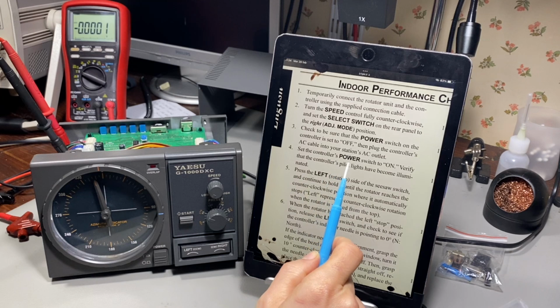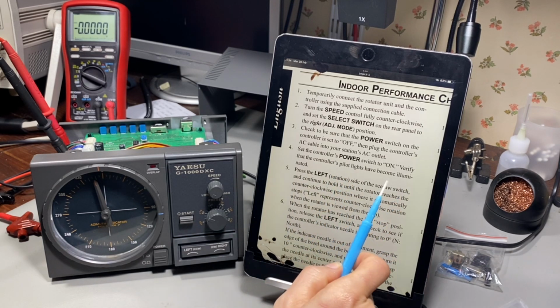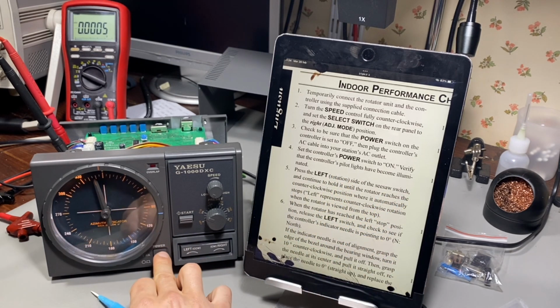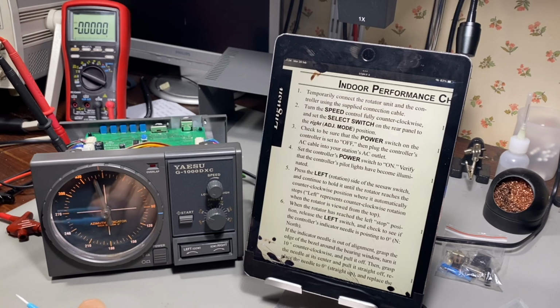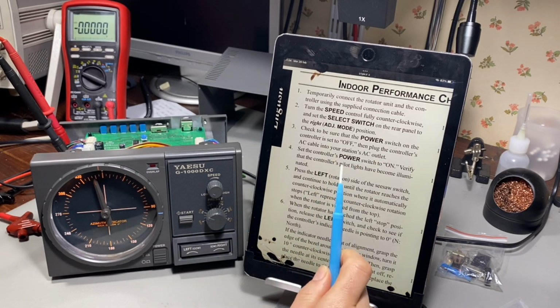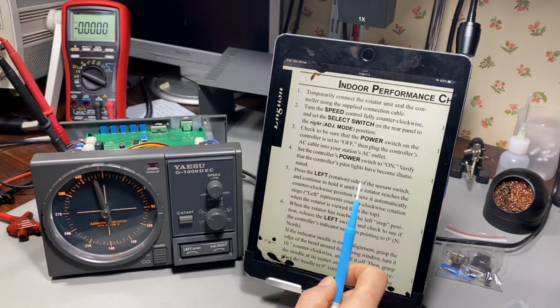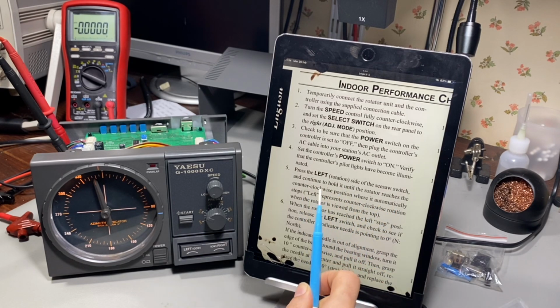Set the control power to on and verify the lights become illuminated. We've got light. Press and hold the left side of the seesaw switch until the rotator reaches the counterclockwise position where it automatically stops. When it reaches the left stop position, release the switch and check if the controller's indicator needle is pointing to 0 north.